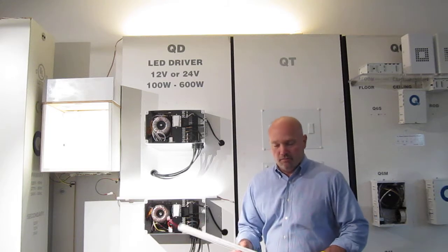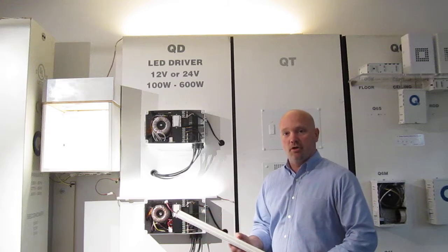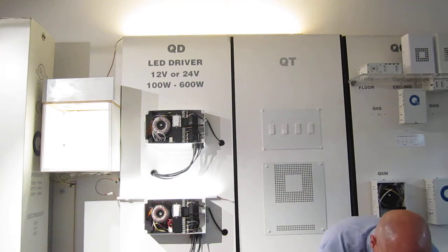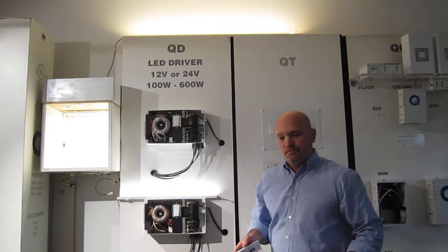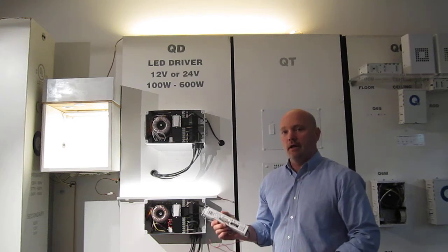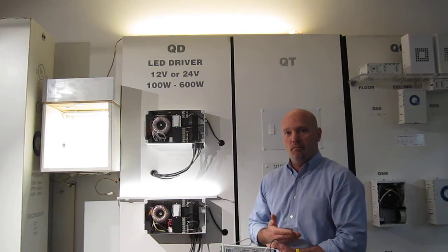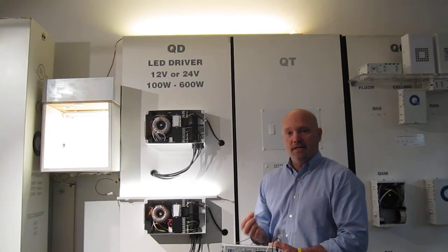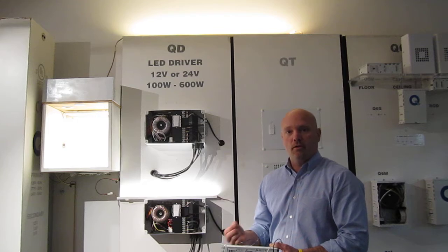So when you look at a constant voltage fixture, it basically has a current limiter on that circuit board that limits the amount of current that can flow through that LED circuit board. Now talking about the drivers themselves, when you look at a driver versus a transformer, an LED constant voltage driver is really nothing more than an electronic transformer that not only transforms the power from one voltage to another, but also takes it from an AC current to a DC current, which the LED circuit boards need to see: a DC forward moving current only.